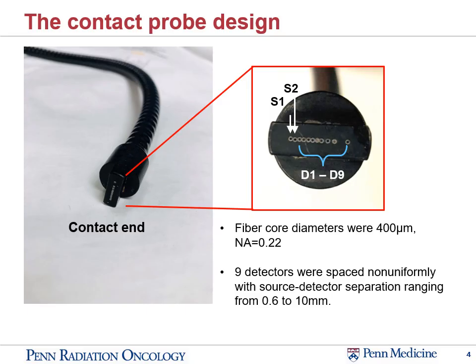For broadband diffuse reflectance spectroscopy, in order to solve for the two important tissue optical properties, which are the absorption and reduced scattering coefficients, we need to have at least two input variables. One of these variables comes from the use of white light spectrum that has different wavelengths, and the second variable comes from the source and detector separations that create different light path lengths.